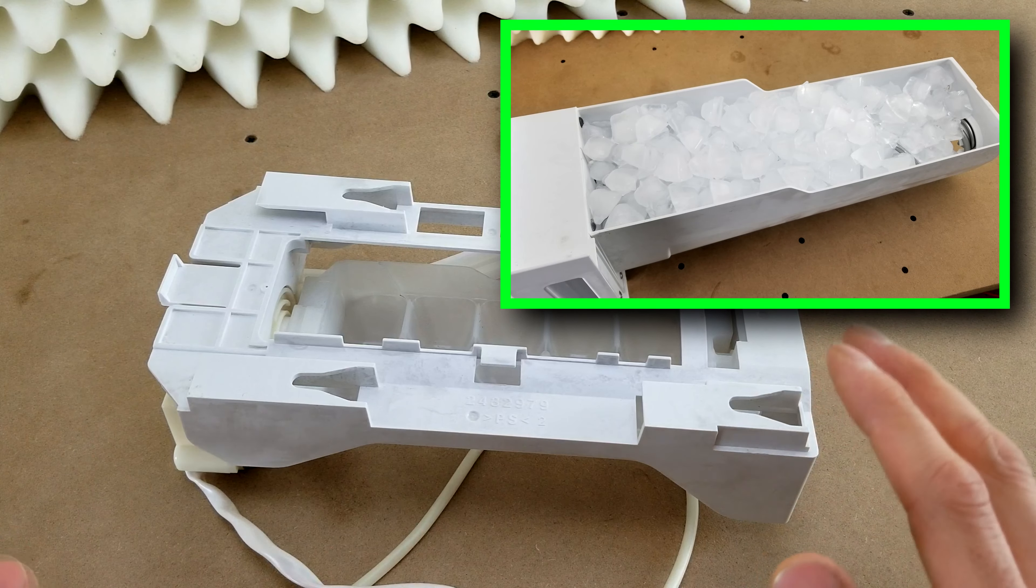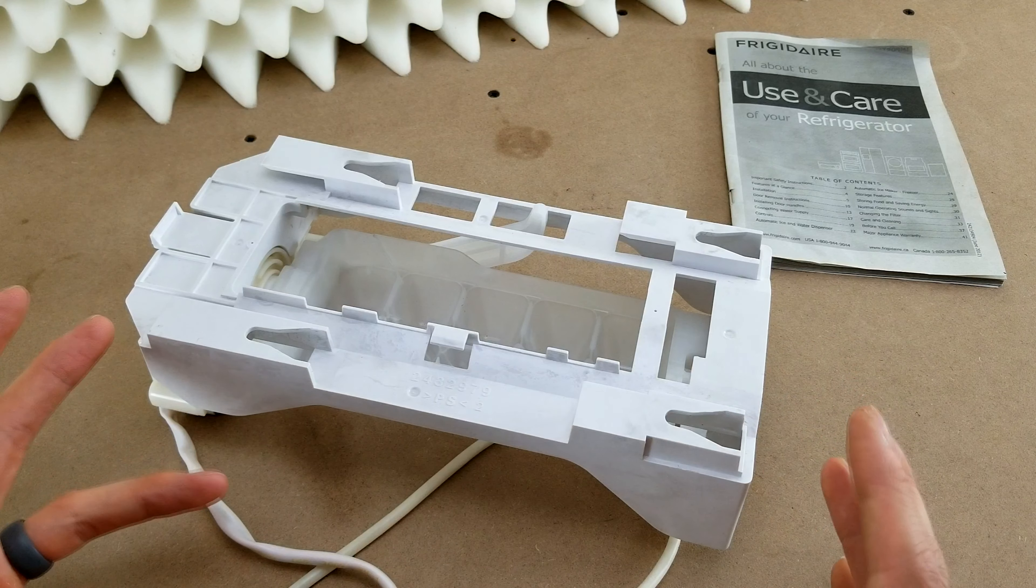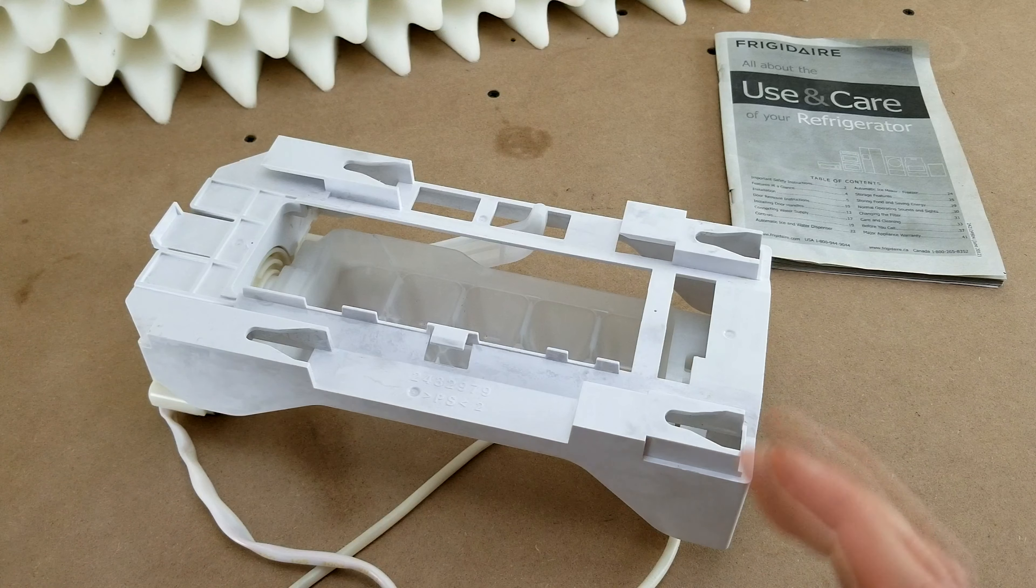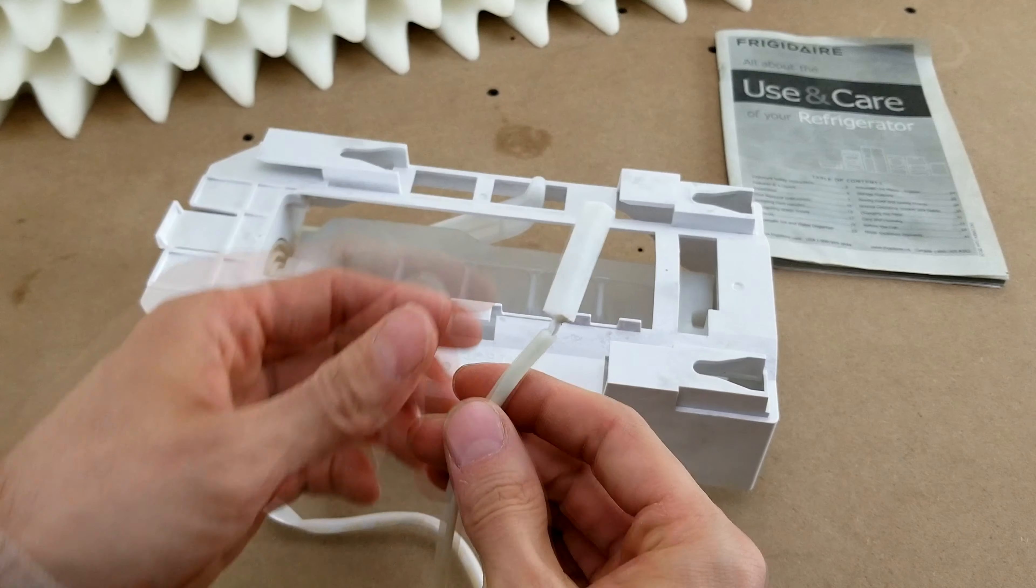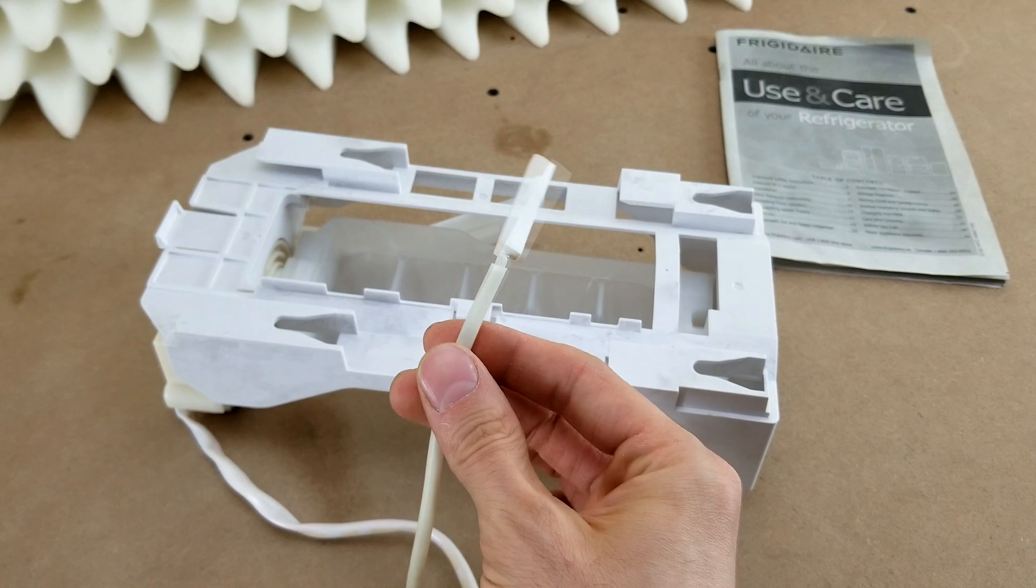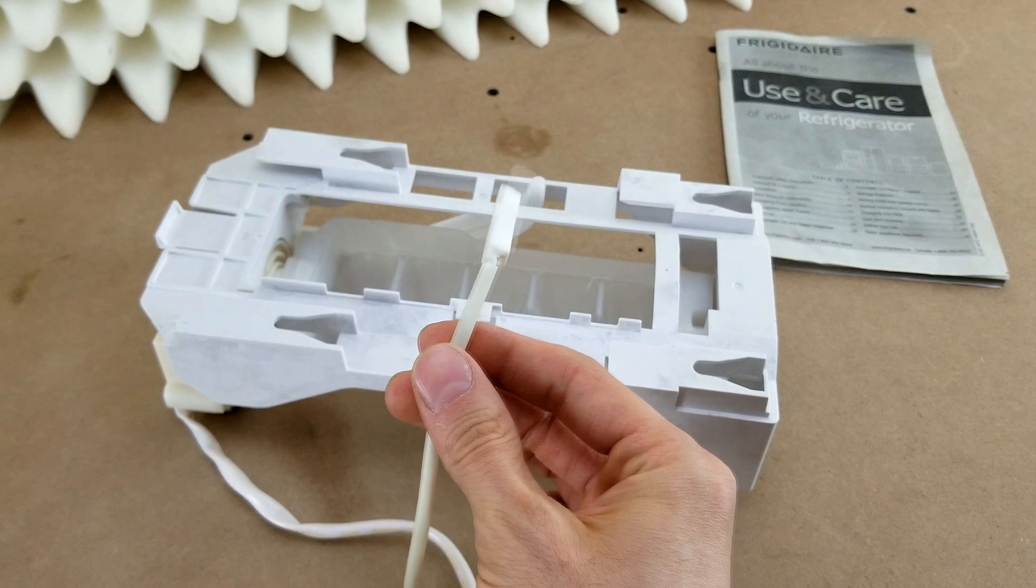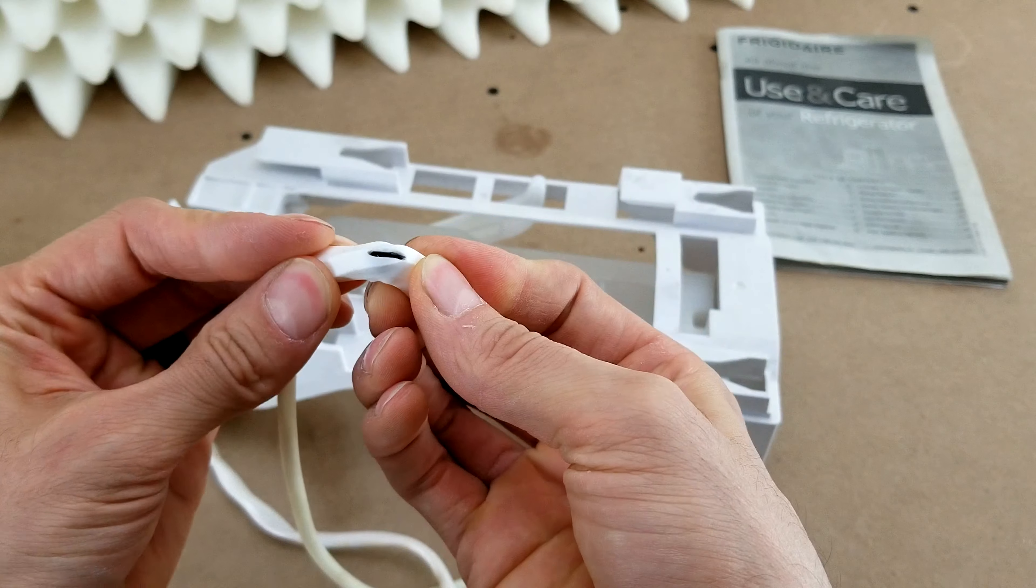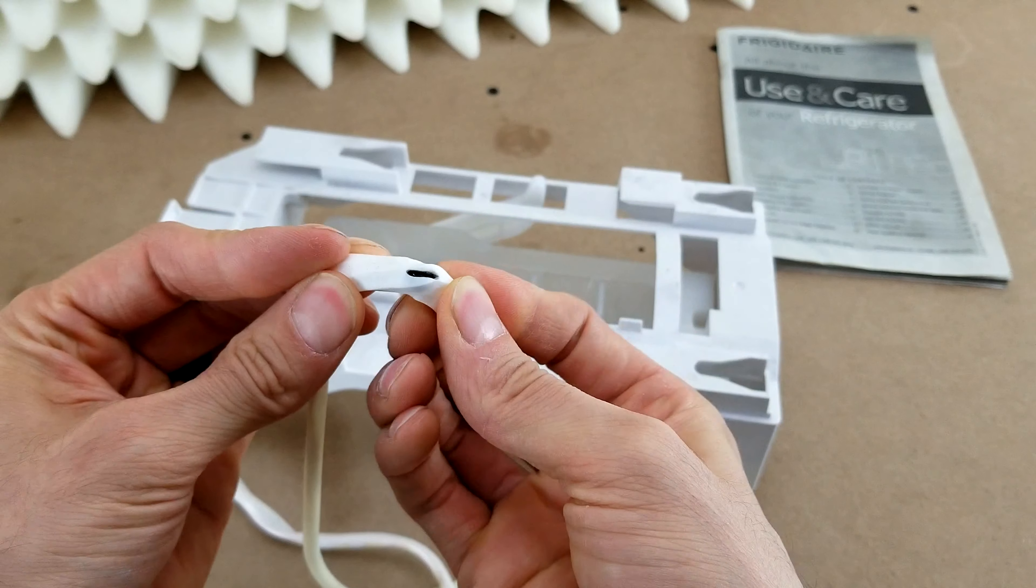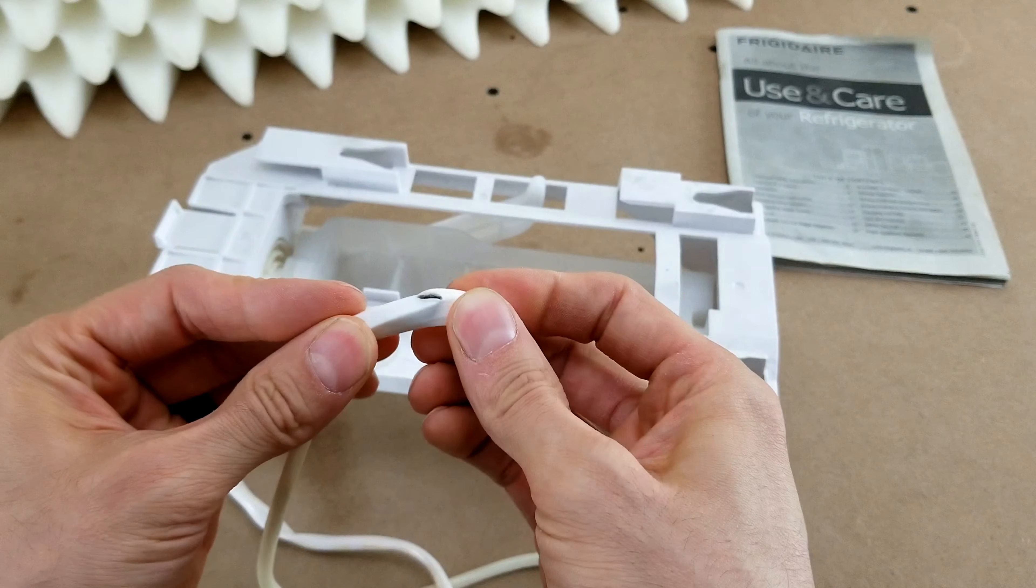So how did I know this thing was bad? As I was taking the ice maker apart, I noticed that there was this little sensor hanging down. I'm not exactly sure where it was supposed to be attached, but when I got looking at it, I noticed there was a little split on it and you can see that it's cracked and damaged.